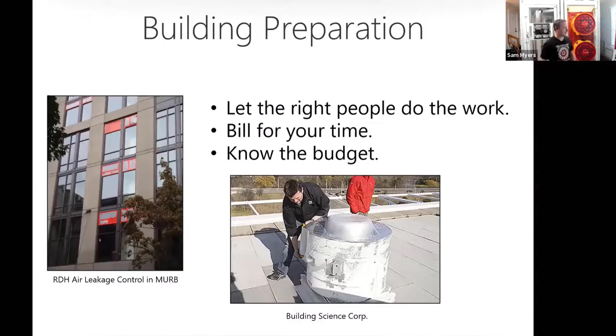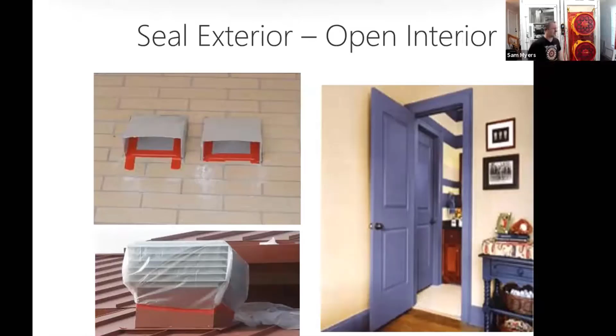For residential buildings, you're going to want to have the whole building open, so all your interior doors. There's a lot more to think about here to get the whole building connected. That's where we open up elevator doors so we can get air down the elevator shaft. All of our stairwells we want to have propped open, and that gives us a pathway to run our tubing too.